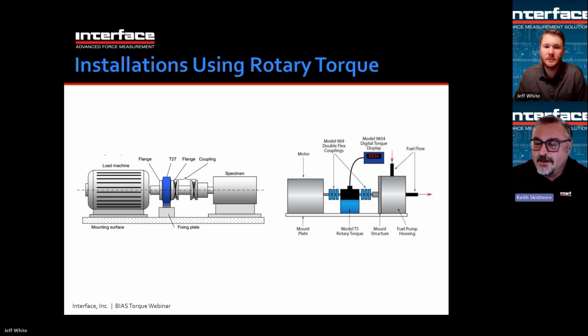You may wonder what the difference is between these two pictures. The couplings on the right side are both double flex, and this pedestal mount sensor needs freedom of movement of its shaft on each side of the torque sensor. When I say movement, I mean radial and angular displacement. On the left side picture, we have a double flex coupling and a floating sensor. The T27 is actually a bearingless sensor. It's supported entirely by the motor shaft, and the double flex couplings on the right just allow for misalignment between the specimen and the motor shaft. Next slide, please.